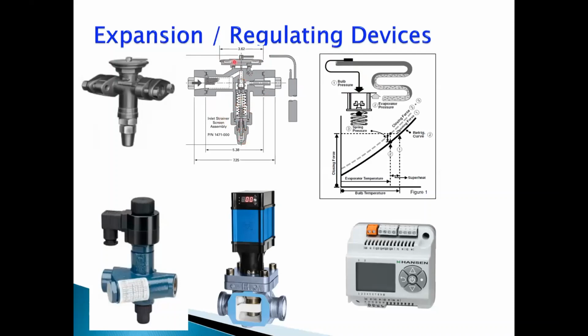So whatever the temperature difference, it operates, this pushes the piston down, and the valve starts opening. And the high temperature liquid which is coming through, because of the smaller orifice, gets expanded and goes to the outlet, to your distributor system. This is a typical expansion valve, functionally almost similar to any thermostatic expansion valve used with other, synthetic refrigerants.